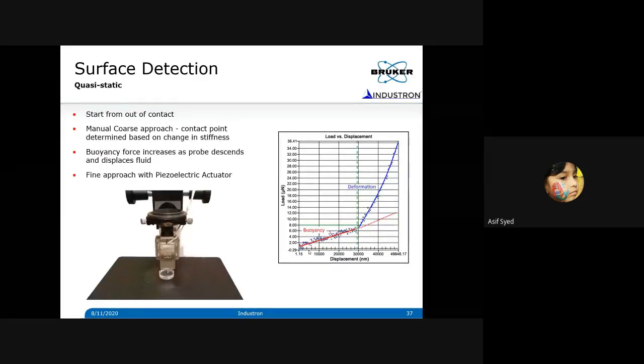There are two ways of making contact and detecting it. In a quasi-static mode, as you bring the probe in, it comes in contact with the water or the liquid in a submerged condition, and we can measure the change in buoyancy. From the change of the slope, we can see where it is actually making contact. That's one way of doing it. I'm also going to present a force modulation technique, where we use the phase shift as you approach as a way of finding the surface of the sample. I'm going to show both approaches in the following slides.